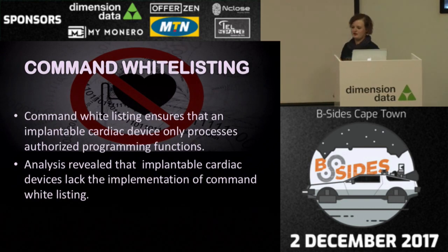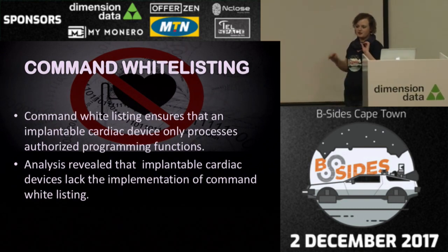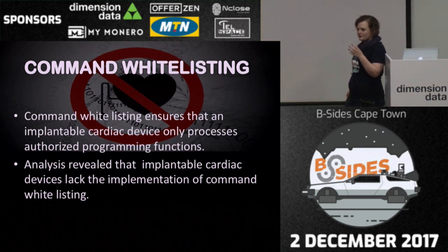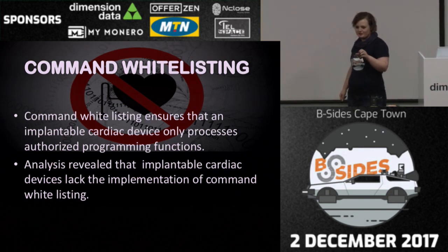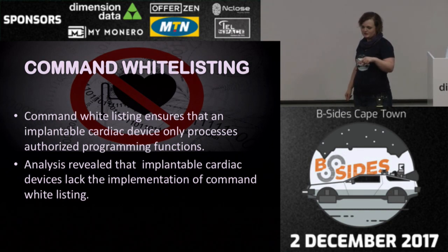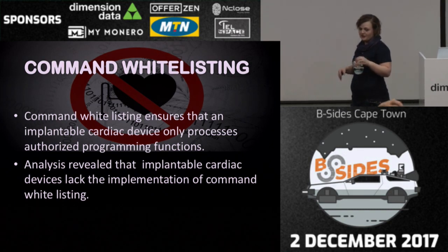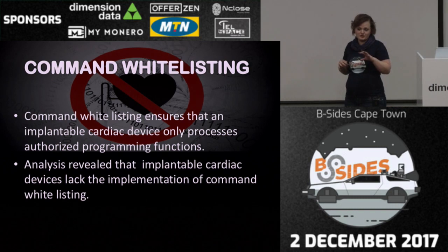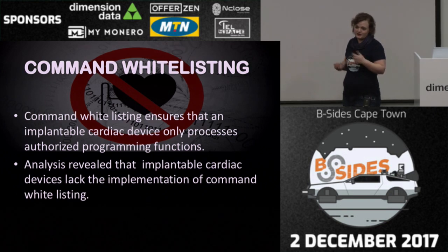Now, this one's a big one for me. Any DevOps person or anyone that does programming would say you need to tell the device what it can accept and can't accept. Well, that is a good idea. However, most medical devices don't have command whitelisting. So if it looks like it, smells like it, acts like it, it will do it.